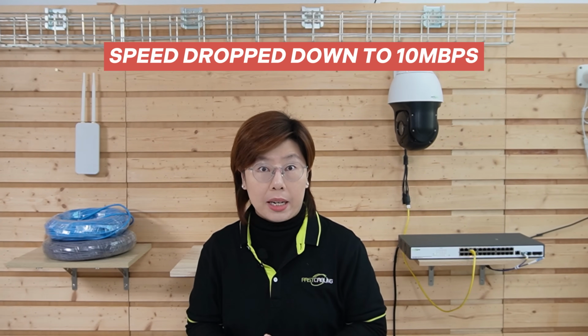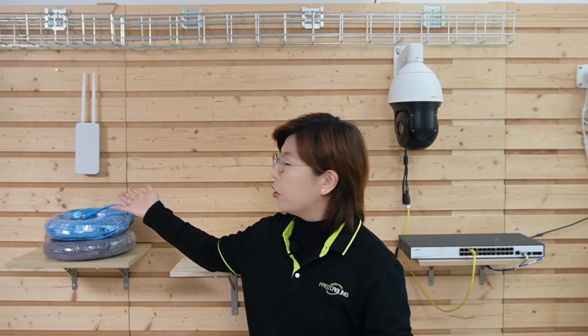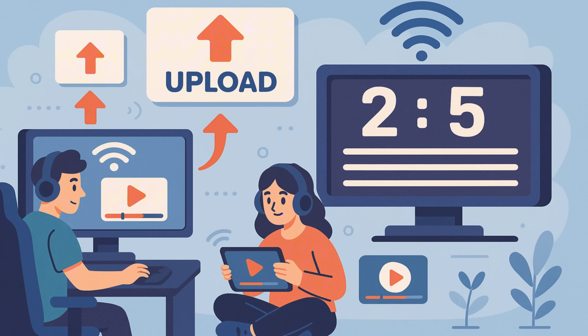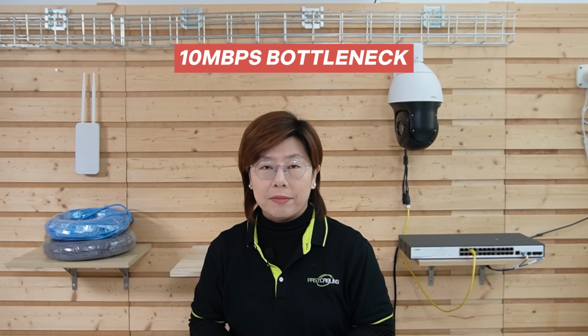Now you might be thinking, can we just flip the CCTV mode on the BT switch again? Negative. CCTV mode on those long-range BT switches usually forces the port down to 10 megabits per second. That's perfect for a single camera stream, but it absolutely chokes a Wi-Fi access point. A modern WAP can push up to hundreds of megabits, especially if you've got players uploading videos and maybe a scoreboard system running over Wi-Fi. So 10 megabits is a bottleneck. So how do we get data and power beyond reach without dumping the port down to 10 meg?